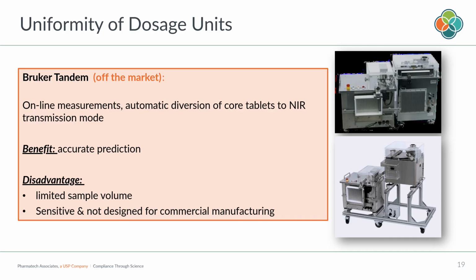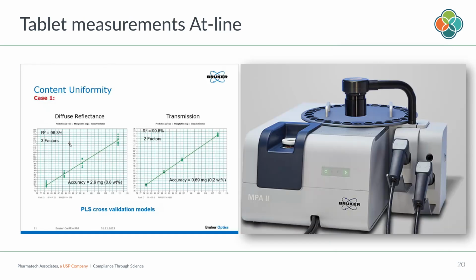It was the limited sample volume, but also the sensitivity, and the design of the unit was very sensitive to a commercial operation. Yeah. So data interfaces have been slow and troublesome with all the data volumes. So in short, it was not maintainable for the price of this unit. So many, if not most, of the installations I know so far out there went back to the offline testing with Bruker MPA as a kind of a standard, for example.